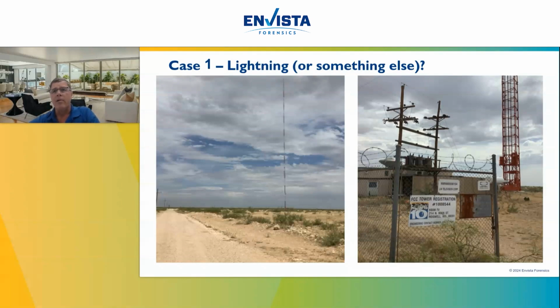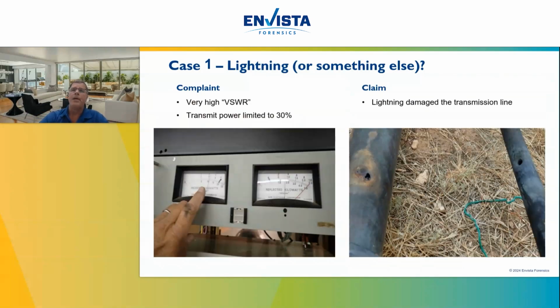When we start thinking about lightning, there's a lightning detection network throughout North America. It's pretty good, but it'll see cloud to ground strikes, and it'll see cloud to cloud strikes, maybe up to 300 feet in the air, 500 feet, something like that, typically. And then above that, maybe not so reliable. So we have to factor that in when we go looking for lightning reports or assessing what the weather conditions were. Keep that in mind. These towers end up a lot higher.